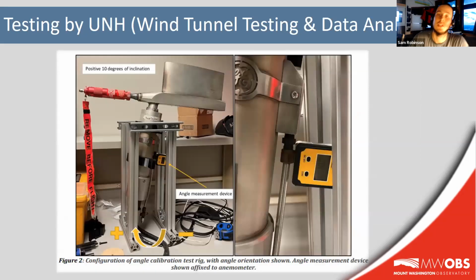Also, before wind tunnel testing, a mounting angle calibration was performed, just to confirm that an orientation offset does apply to this type of pressure transducer. Basically, the orientation or angle of the pressure transducer plays a role in the measurement of the pressure. So in operation, we apply a correction factor for the angle at which they're oriented inside the body. And this lab test just simply confirms that the correction factor does in fact play a role in the accuracy.